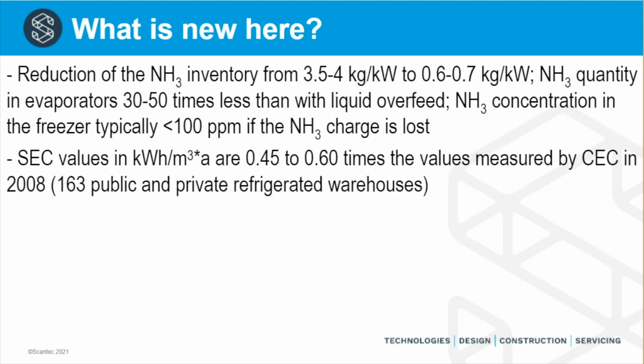The specific energy consumption values, there'll be more to say about that later, are typically half of conventional plants. In some cases, it's not quite that dramatic. Sometimes it's only 1.4 times lower, and there are instances where it is 10 times lower if the liquid overfeed plant is very poorly designed or operates extensively in part load or both.